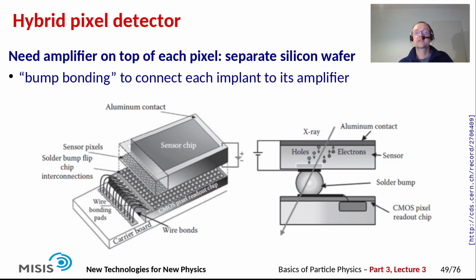And the way this is usually realized in so-called hybrid pixel detectors is that you have two separate wafers of silicon. So there is one wafer that has the sensitive volume, so the pixel detector itself, and then there is a second wafer which has the front-end amplifiers. And the two are joined together by so-called bump bonding, where you have one of these little ball bumps in between each pixel on the detector and the corresponding connector on the readout chip.